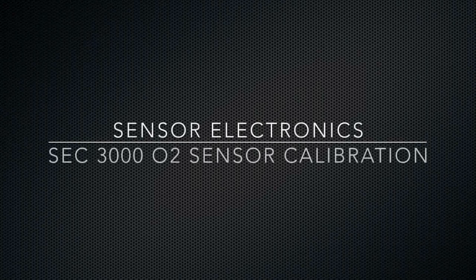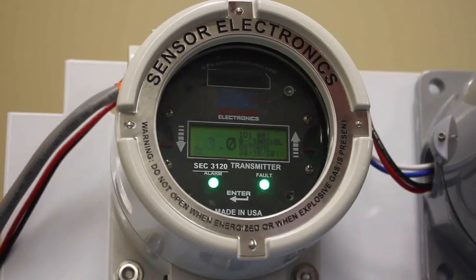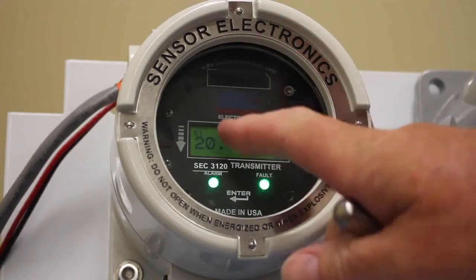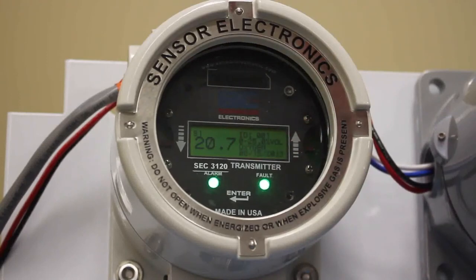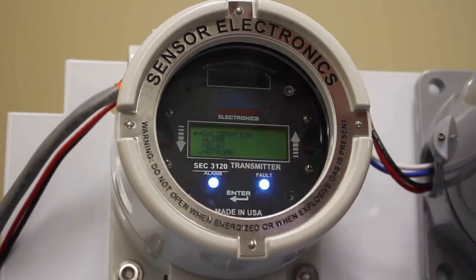In this video, what we'll show is the calibration of the SEC 3000 sensor. I've chosen an oxygen sensor to calibrate. It's located on sensor number 1 on the 3120 transmitter. And so first, what you'll do is you'll take your magnet, go to enter, and then arrow down to calibration, and then select enter. And then you select the sensor that you want to calibrate, which is sensor 1. So we do want to calibrate that.